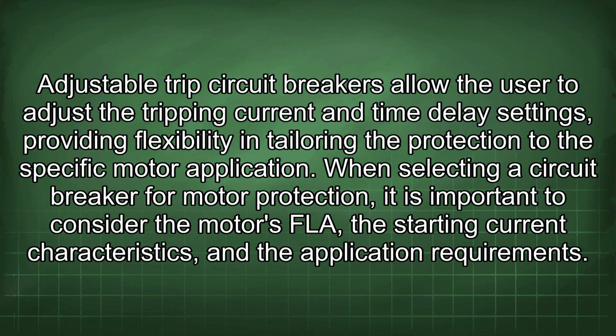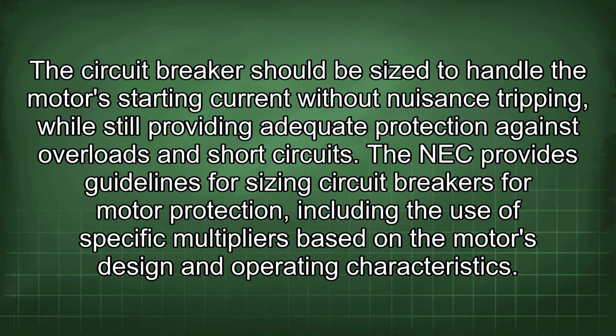When selecting a circuit breaker for motor protection, it is important to consider the motor's FLA, the starting current characteristics, and the application requirement. The circuit breaker should be sized to handle the motor's starting current without nuisance tripping, while still providing adequate protection against overloads and short circuits. The NEC provides guidelines for sizing circuit breakers for motor protection, including the use of specific multipliers based on the motor's design and operating characteristics.